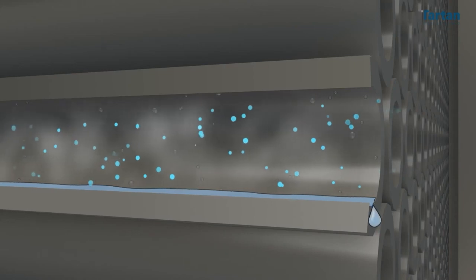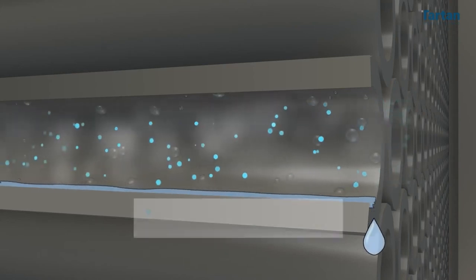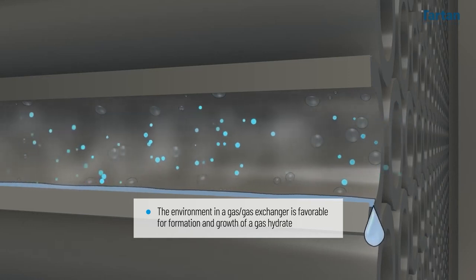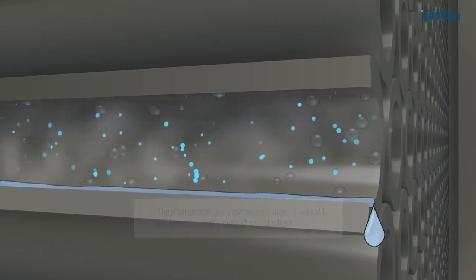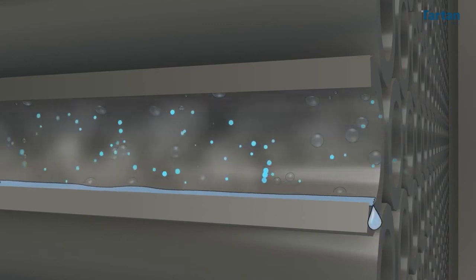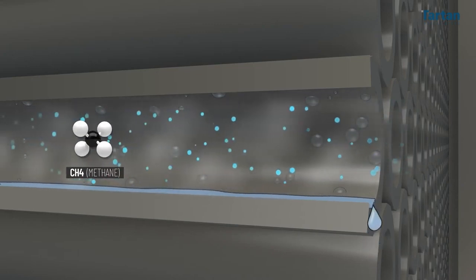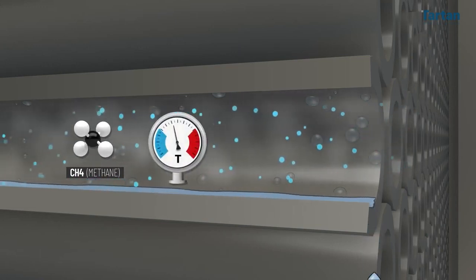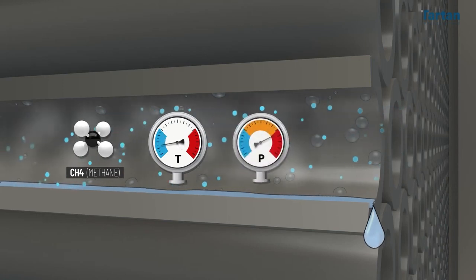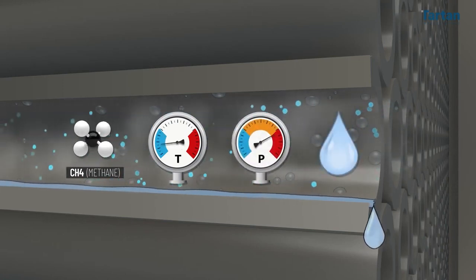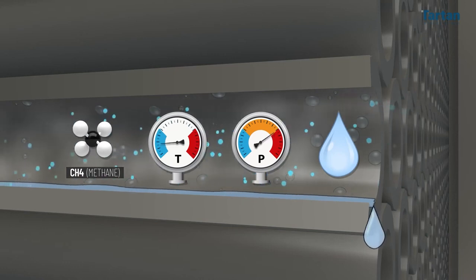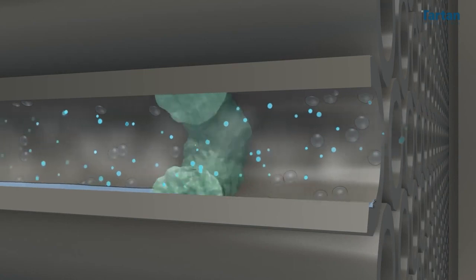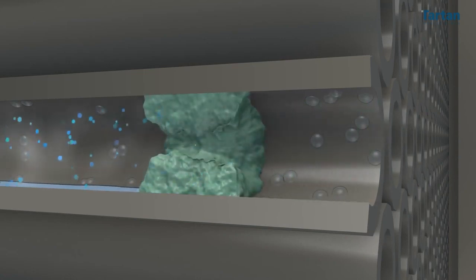As previously discussed in the section on hydrate formation, the environment in a gas-gas exchanger is favorable for formation and growth of a gas hydrate. The host molecule, mostly methane, is abundant in the process gas. As the gas moves through the exchanger, the temperature is dropping, operating pressure is moderately high, and liquid water is condensing out of the gas — all favorable conditions for hydrate formation. If hydrates are formed, they can block the tubes and stop the gas flow.